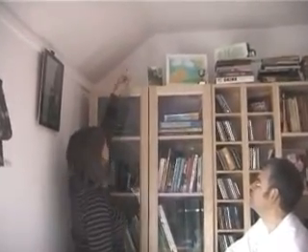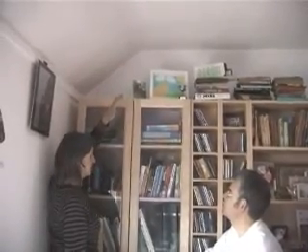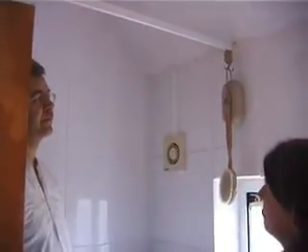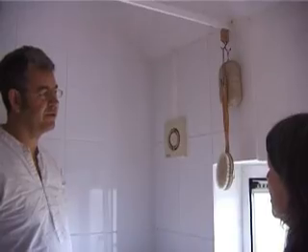I notice you've got a sloping ceiling at the edge of the room here — that's going to be a lot of heat loss because there's no insulation between the plaster and the tiles; there's just no space. Your loft insulation will stop it just as the ceiling starts to come down. And you've got mold spots here — this is an illustration of the fact that this bit of roof is going to be a lot colder than your wall or ceiling, so the moist air in the bathroom will condense out on that piece of ceiling, and that's where you get the mold from.